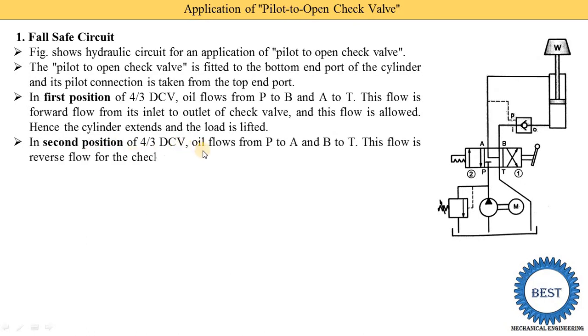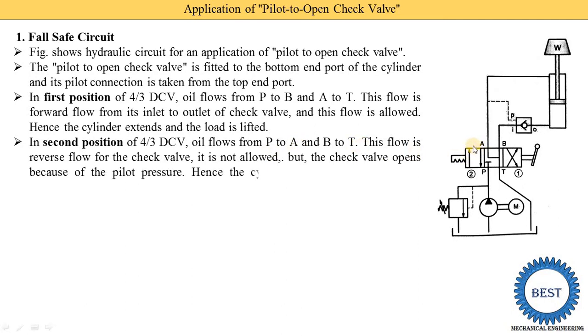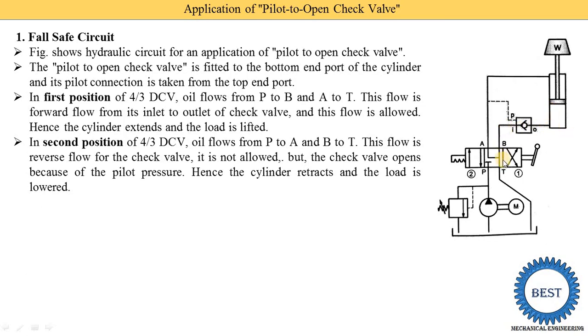In the second position of the 4/3 DCV, oil flows from P to A and B to T. The P port is connected to A, oil goes to the top end part, applies pressure on the piston, and the piston starts to move downward. This is reverse flow for the check valve and is normally not allowed. However, the check valve opens because of the pilot pressure — the pressure in the top end line is higher, so this opens the check valve. When the check valve opens, pressurized oil flows from the bottom end part to port B. Hence the cylinder retracts and the load is lowered.